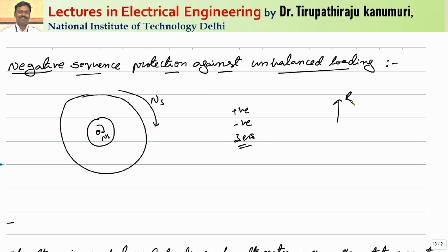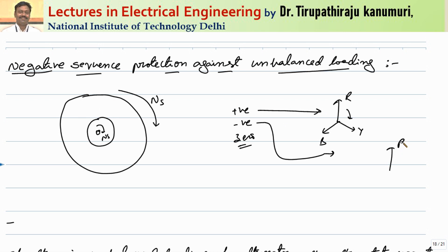The positive sequence component — R, Y, and B — rotates in the forward direction, producing a rotating magnetic field. The negative sequence component rotates in the opposite direction. The zero sequence components are in phase with each other and will only flow if the fault is associated with ground. If not grounded, only positive and negative sequence components are present.